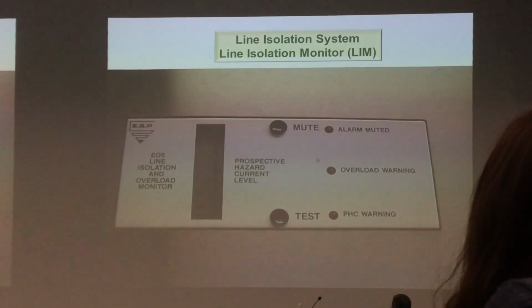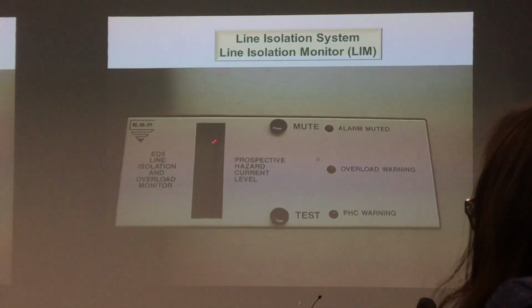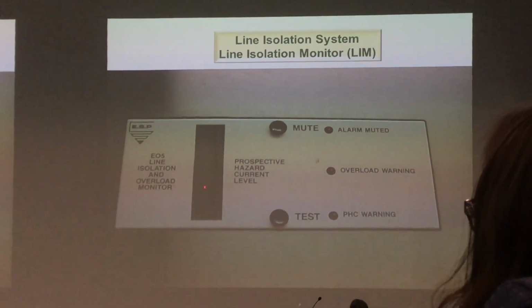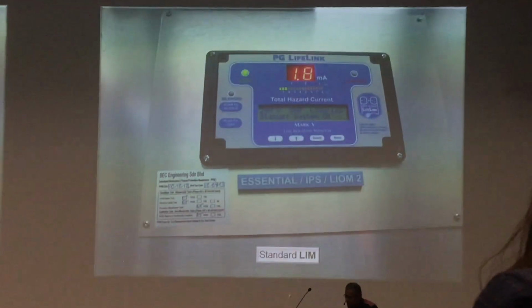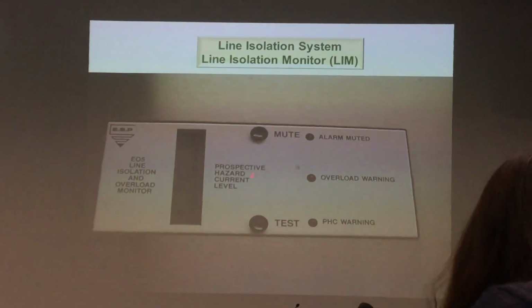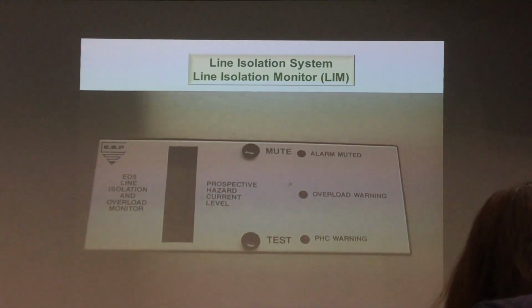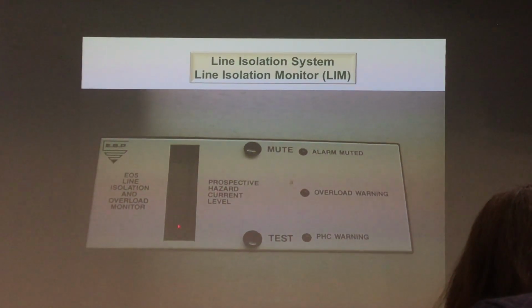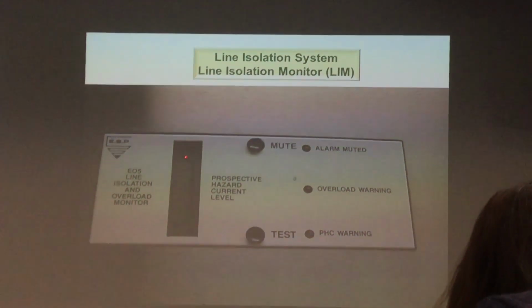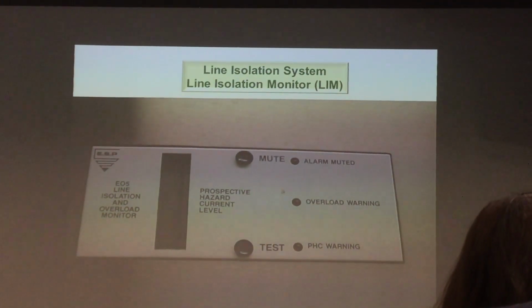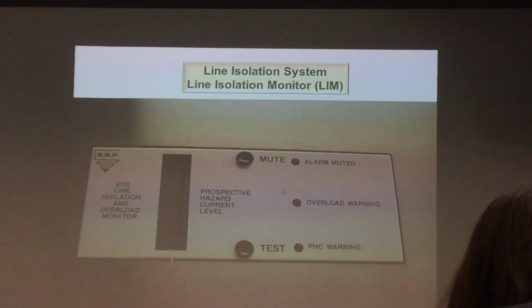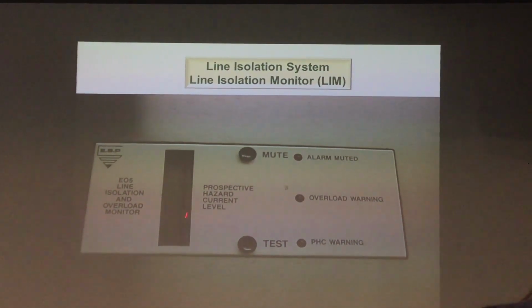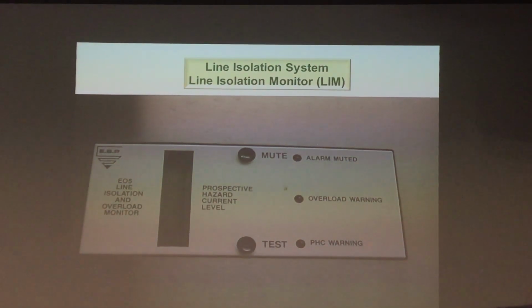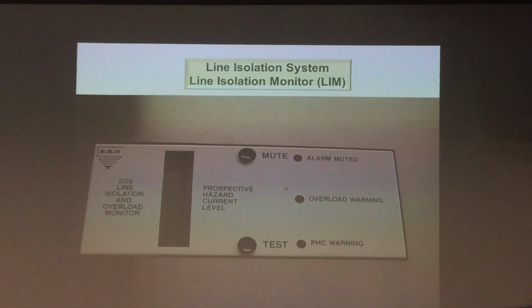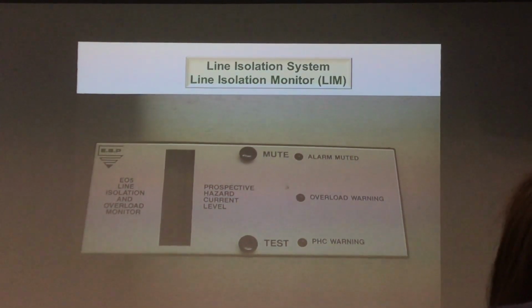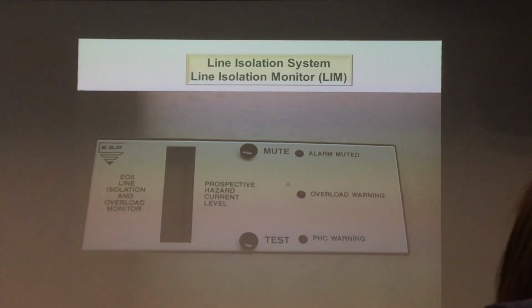Now the LIM, this is the one I want to show you. This is in the OT, this is the LIM, LIOM, or LIS, all the same. Here there's an indicator to show the current flowing to the OT, up to a maximum of 5 mA — I'll show you in the electronic device later. If the current used is more than 5 mA, it will give an alarm, meaning you are overusing, using more than 5 mA at any time. So this will blink, the alarm will sound. This is the old one.